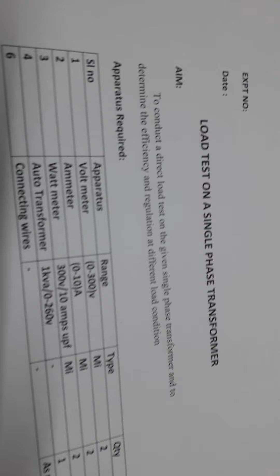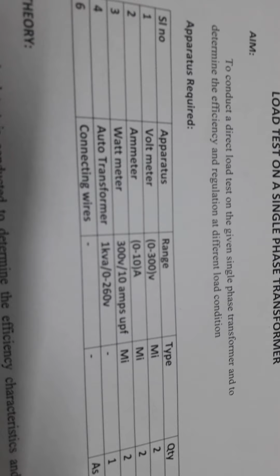The third experiment for machines is the load test on a single phase transformer. Here the aim is to conduct a direct load test and to determine efficiency and regulation at various load conditions. The apparatus required include voltmeter, ammeter, wattmeter, auto transformer and connecting wires.